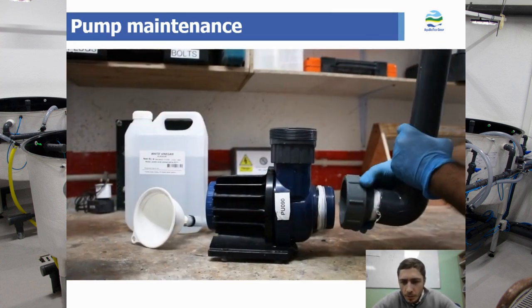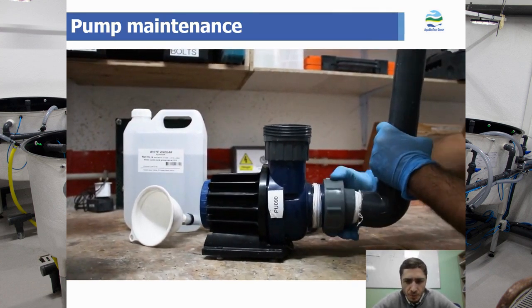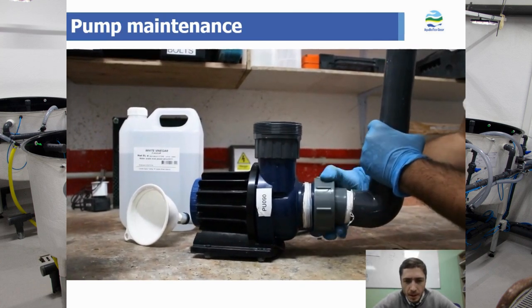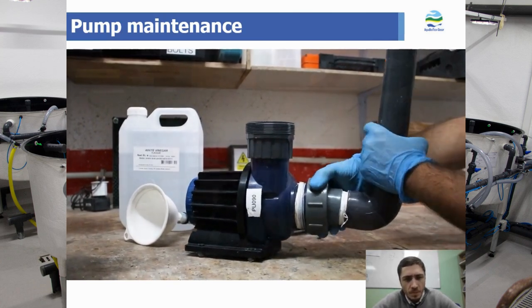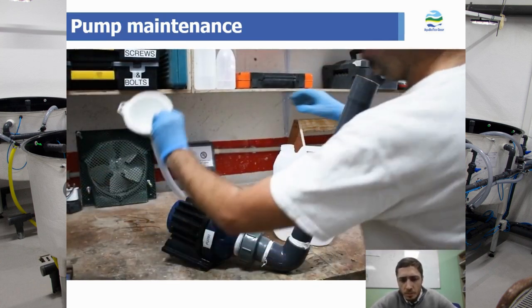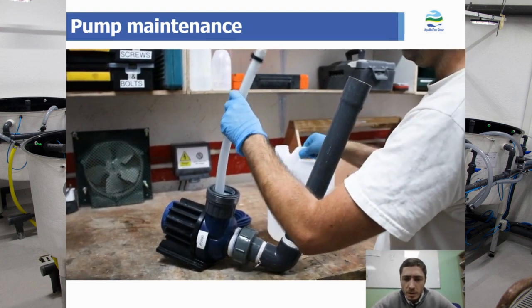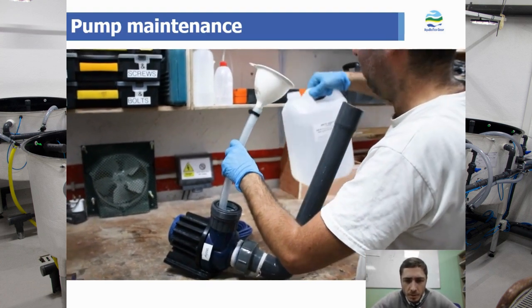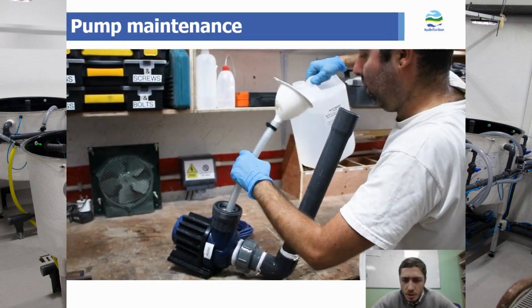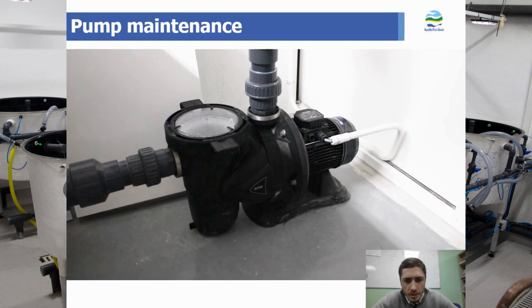Every 12 months you want to perform this decalcification procedure. Over time pumps will develop calcification, particularly in warm marine systems. So just seal up one end, make sure there are no leaks, and then fill up from the other end. We leave this for two to three hours, up to a maximum of 24 hours — so just overnight would be suitable.